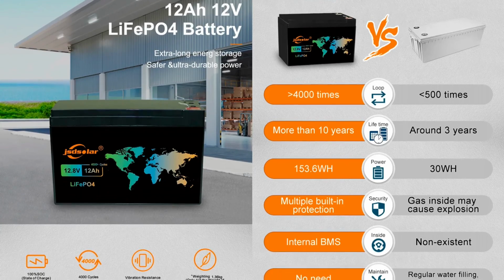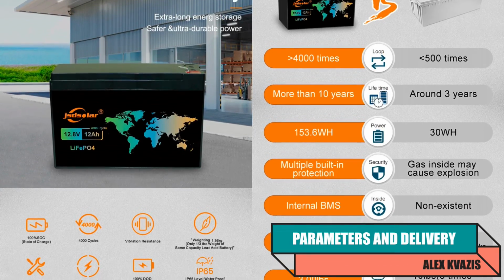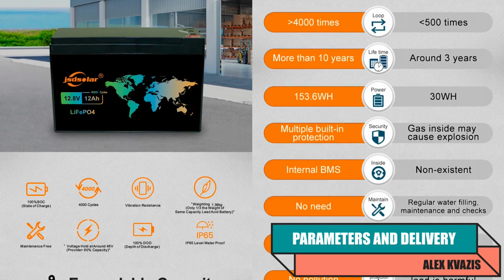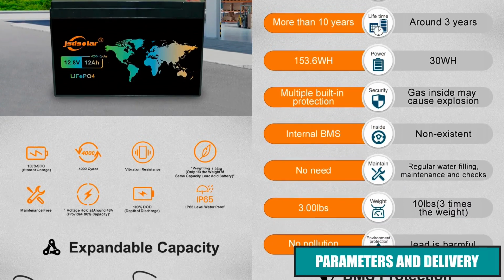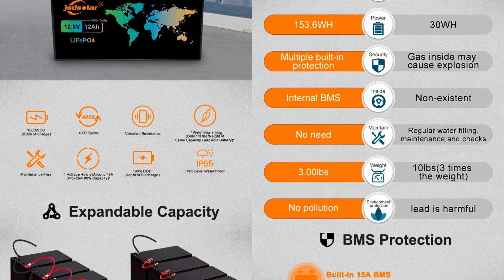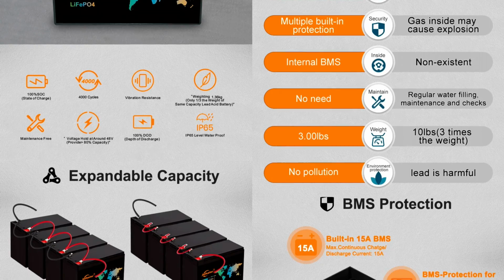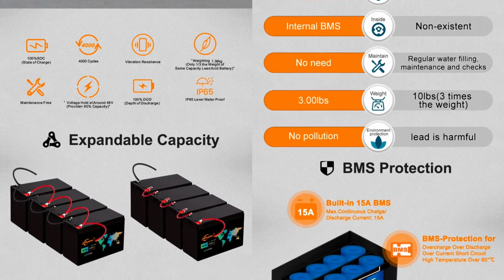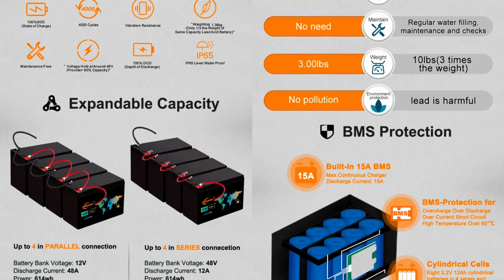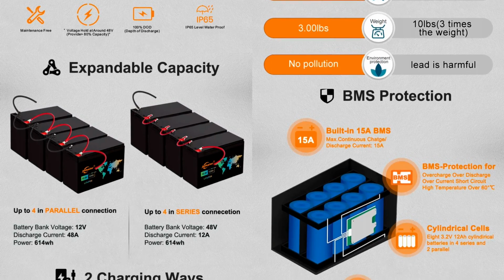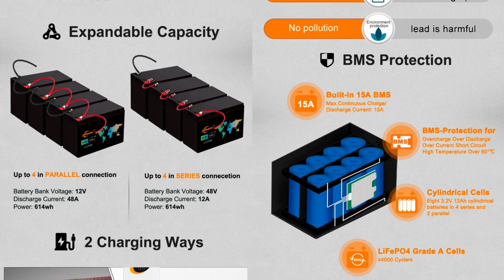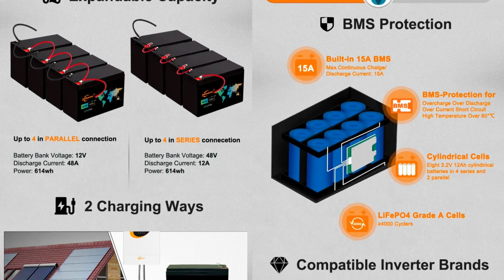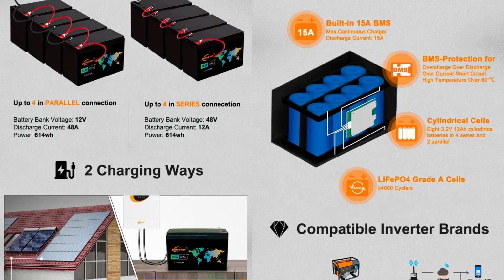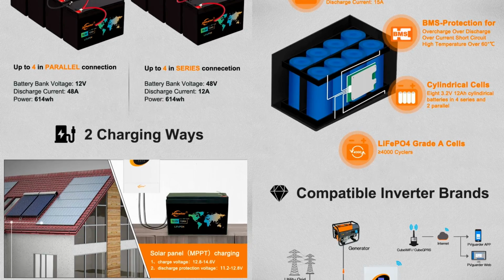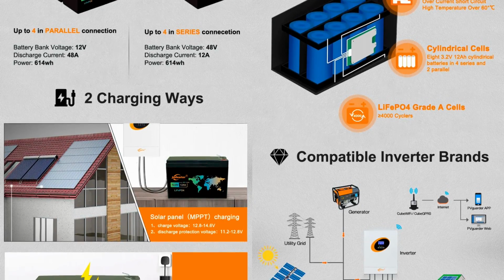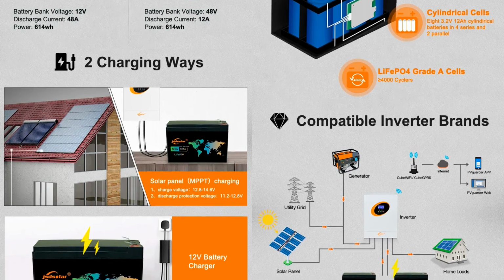Battery type, lithium iron phosphate. Number of discharge cycles, no less than 4,000. Built-in BMS controller, protection against short circuit, overcharge, and deep discharge. Nominal voltage, 12.8 volts. Nominal capacity, 12 amp hours, 153.6 watt hours. Charge voltage, 14.6 volts. Maximum charge/discharge current, 12 amps. Standard charge/discharge current, 6 amps. Discharge voltage, 11.2 volts. Case size, 151 by 98 by 100 millimeters. Protection class, IP65.